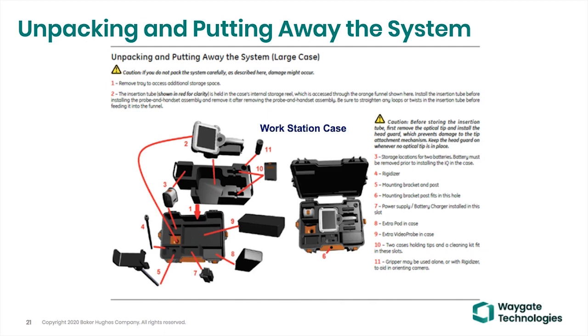Before you store the system and put it in this case, make sure you have a head guard installed on the camera. I've had people say, now, why is that important? So let's think about that. We put the system away. It has a 3D phase measuring tip on there, or any of our optical tips besides the head guard, and they have an O-ring in the proximal body to keep light out.